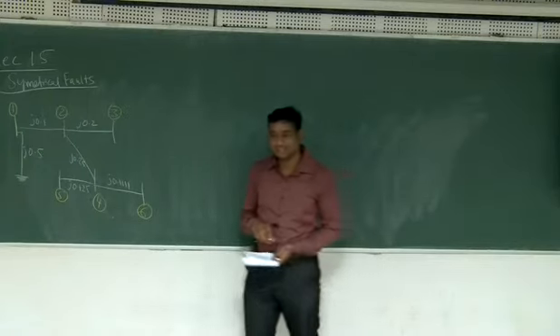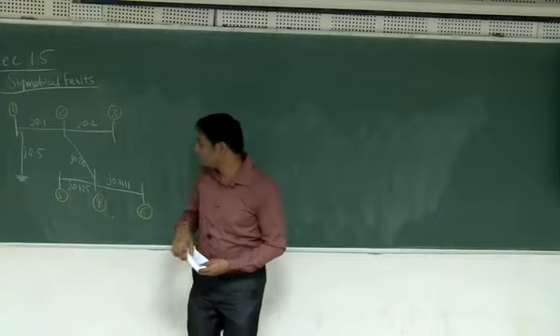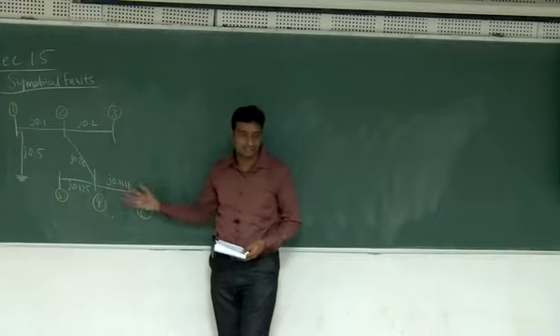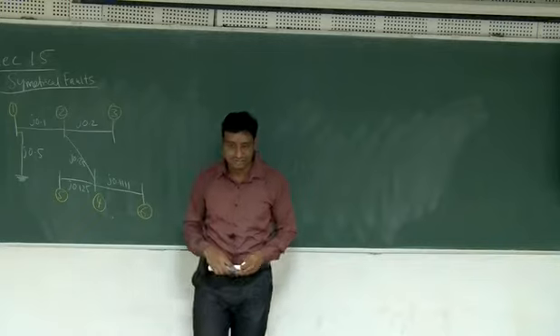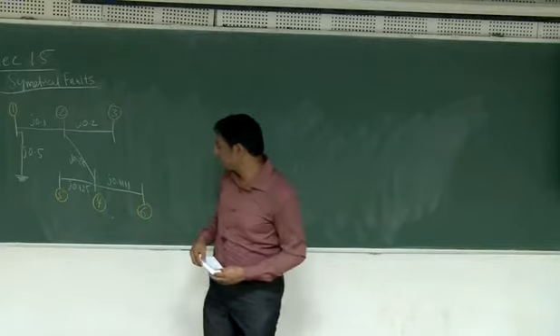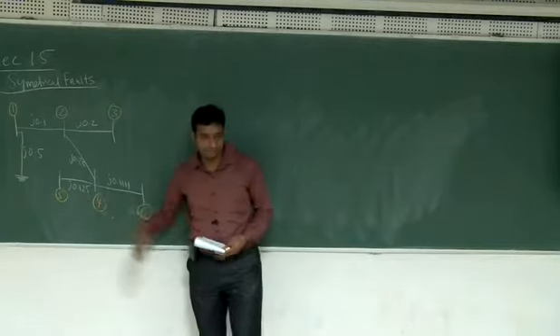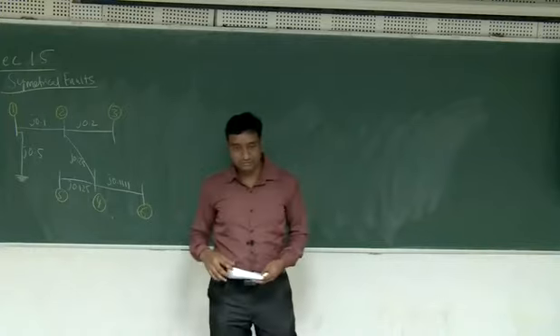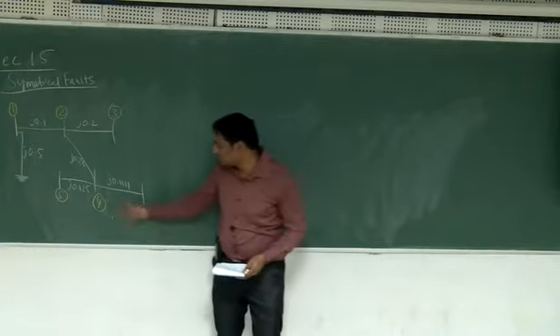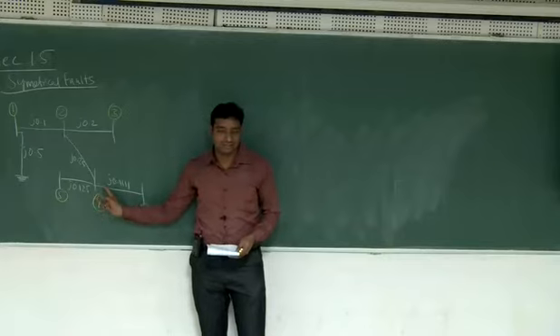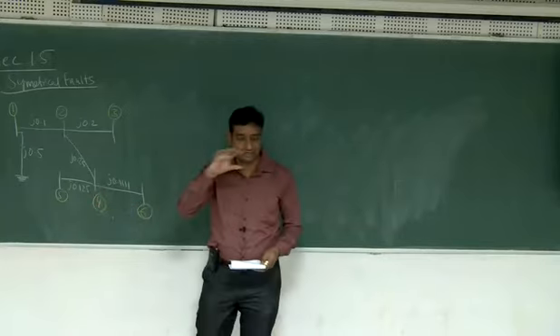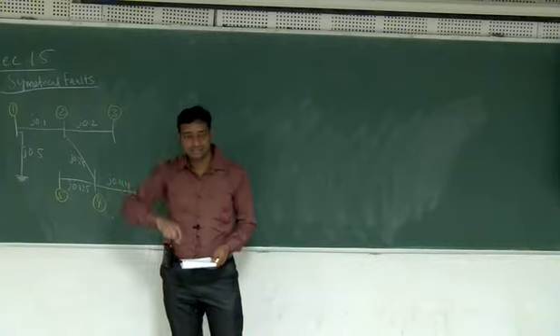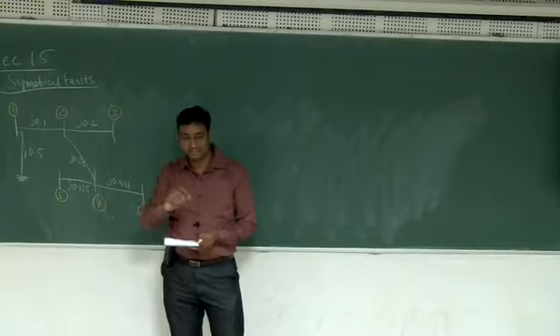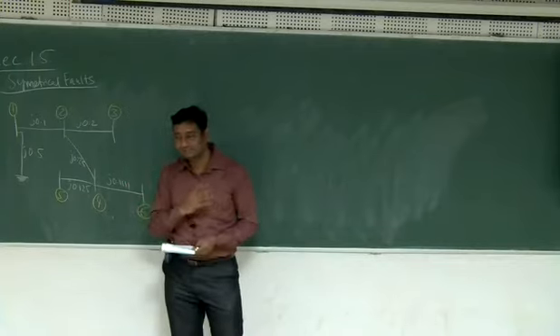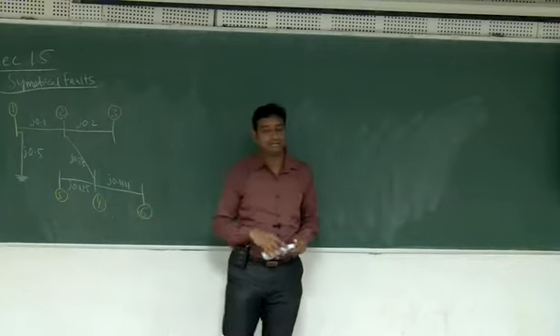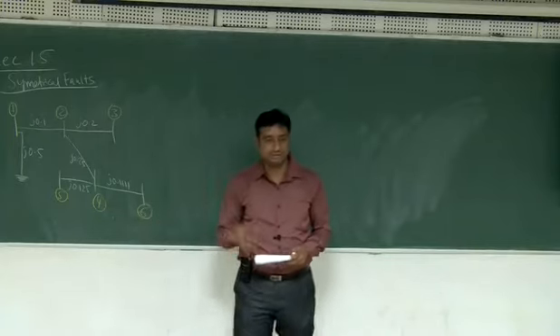So base case is a situation where you have generators and loads and network, and in the base case some powers are flowing. Over and above that base case, if there is a fault, what happens? So first of all, what is a fault? A fault is that whenever there is high voltage bus bars or high voltage equipment, high voltage device, that is suddenly short circuited to the ground or to each other, and then unintentionally some high current will flow. Because of that high current, we call it a short circuit or fault.